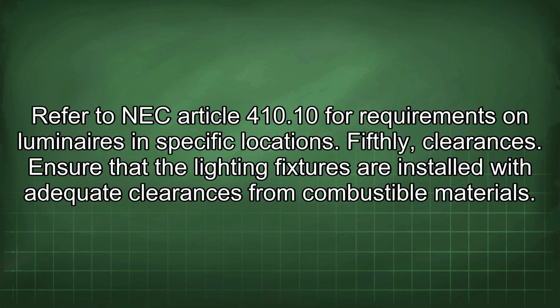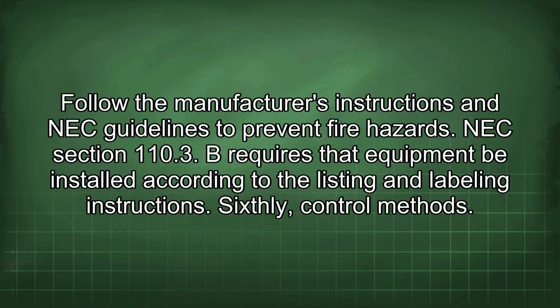Fifthly, clearances. Ensure that the lighting fixtures are installed with adequate clearances from combustible materials. Follow the manufacturer's instructions and NEC guidelines to prevent fire hazards. NEC Section 110.3(B) requires that equipment be installed according to the listing and labeling instructions.